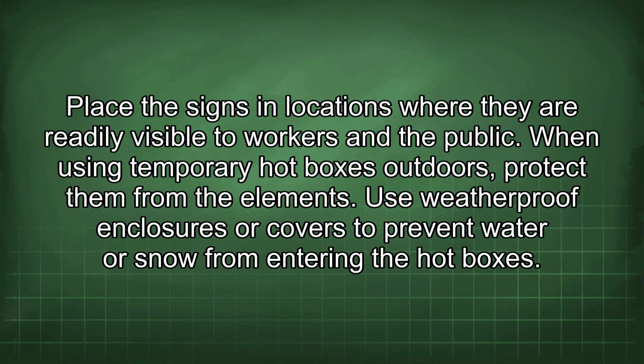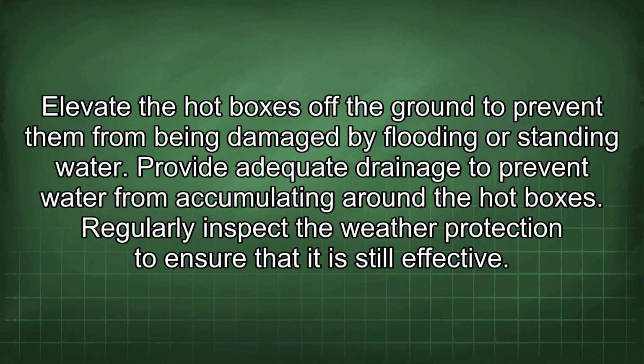When using temporary hotboxes outdoors, protect them from the elements. Use weatherproof enclosures or covers to prevent water or snow from entering the hotboxes. Elevate the hotboxes off the ground to prevent them from being damaged by flooding or standing water. Provide adequate drainage to prevent water from accumulating around the hotboxes. Regularly inspect the weather protection to ensure that it is still effective.